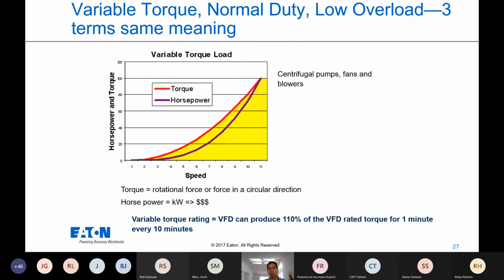Let's compare that to a variable torque application. This would be an application where you have 110% of torque for 1 minute every 10 minutes. And this is an important graph to look at because you can use a constant torque VFD on a variable torque application, but not the other way around. And there are more benefits on constant torque, such as higher heat rating and being able to withstand more, with a longer lifespan than a variable torque VFD. So when in doubt, please always try and apply the constant torque formula.